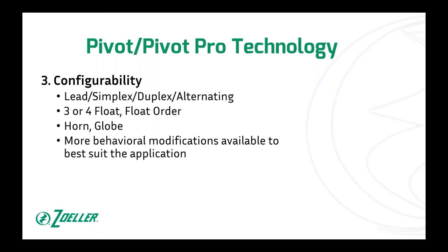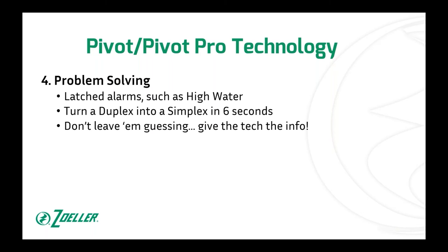Third, configurability. On a duplex panel, you can configure it as lead-lag, simplex, duplex, or alternating. You can make it three or four float, determine the float order — stop, lead, lag, high or stop, lead, high, lag — and configure whether the horn and globe are active versus latching. There are additional behavioral modifications programmable via thumb drive on Pivot or via the LCD button menu on Pivot Pro.